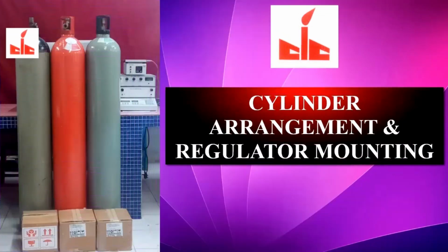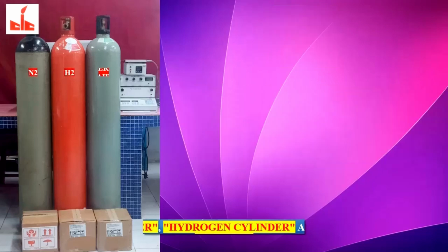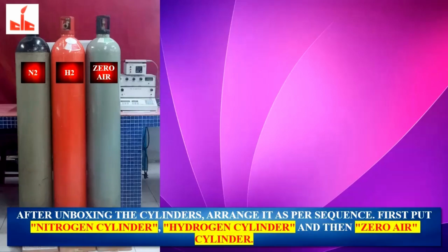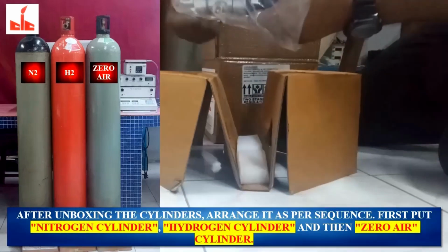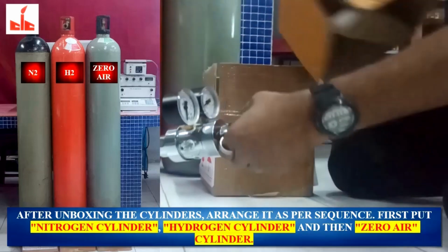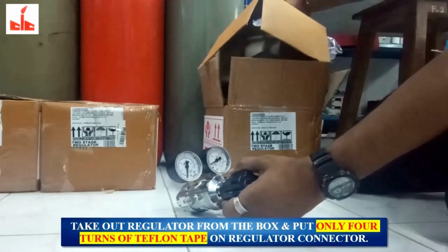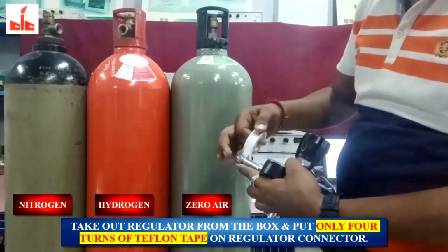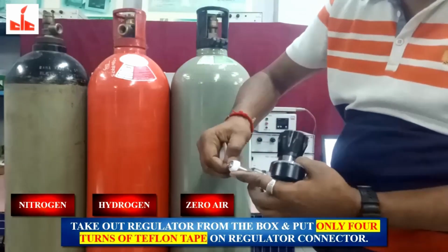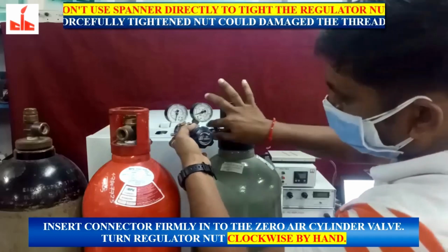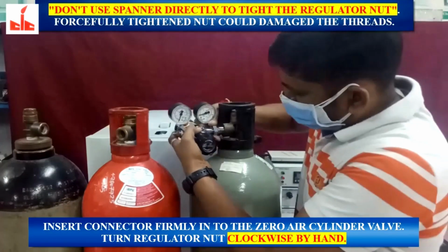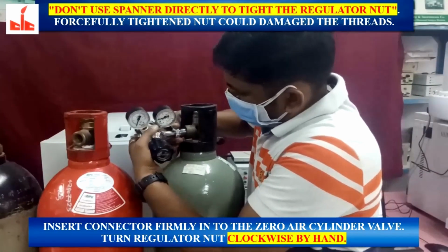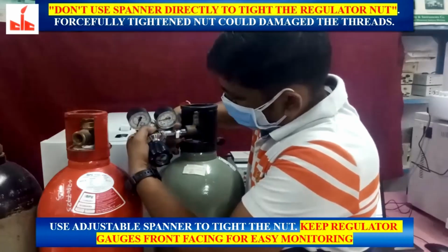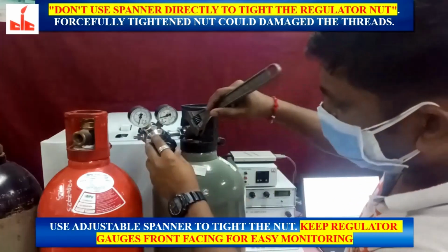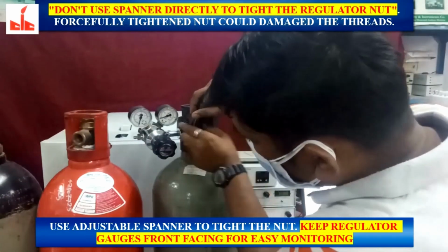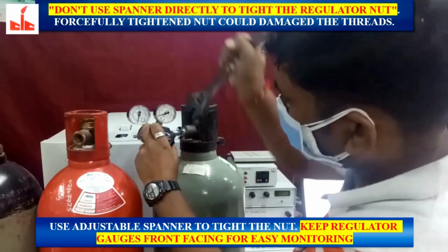Cylinder arrangement and regulator mounting. After unboxing the cylinders, arrange them as per sequence. First put the nitrogen cylinder, hydrogen cylinder, and then the zero air cylinder. Take the regulator out of the box and put only 4 turns of Teflon tape on the regulator connector. Insert the connector firmly into the zero air cylinder valve. Turn the regulator nut clockwise by hand. Don't use a spanner directly to tighten the regulator nut. Forcefully tightened nut could damage the threads. Use an adjustable spanner to tighten the nut. Keep regulator gauges front facing for easy monitoring.